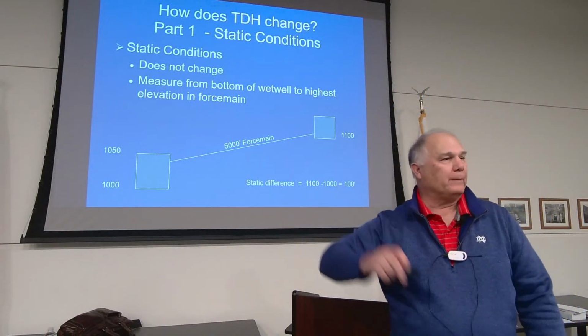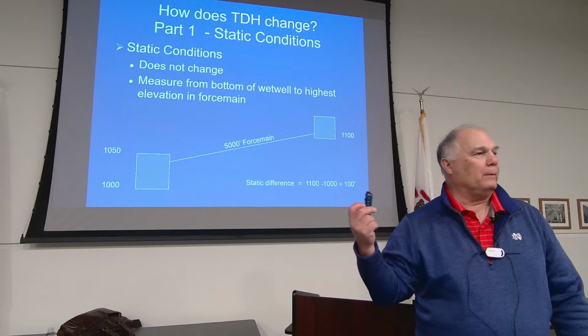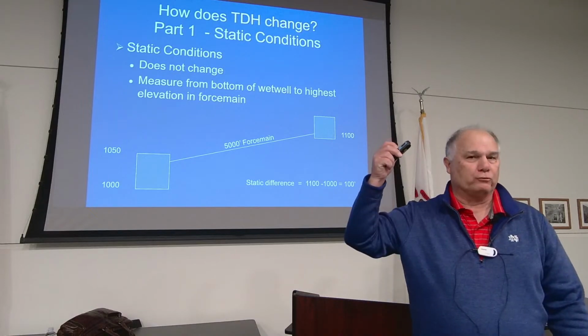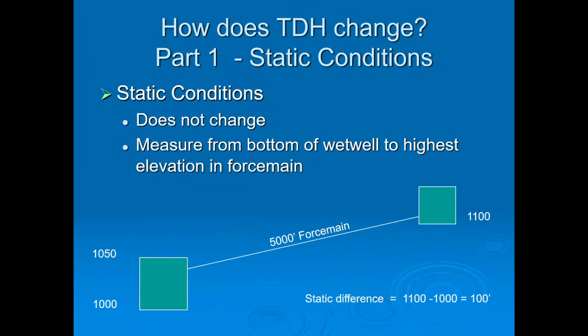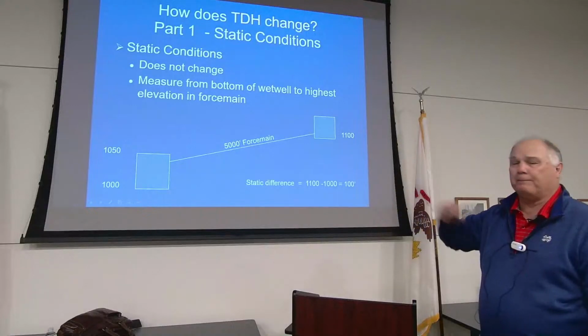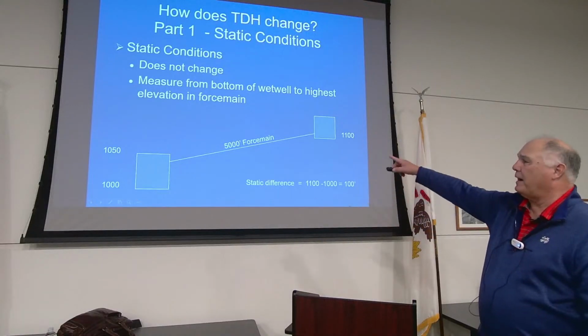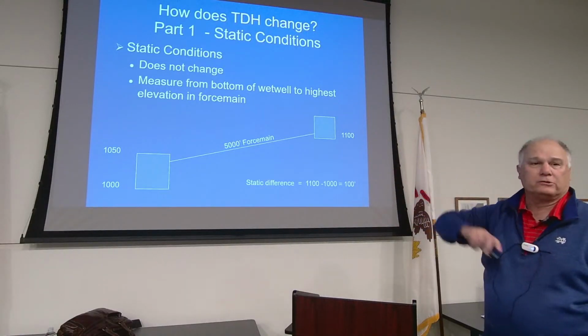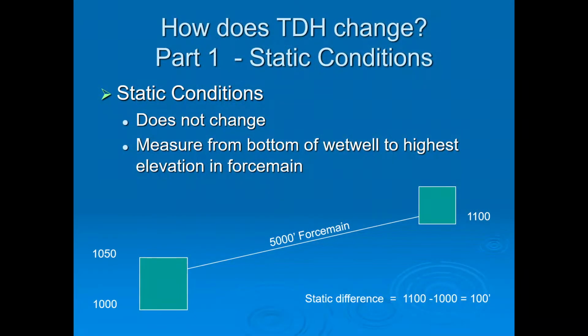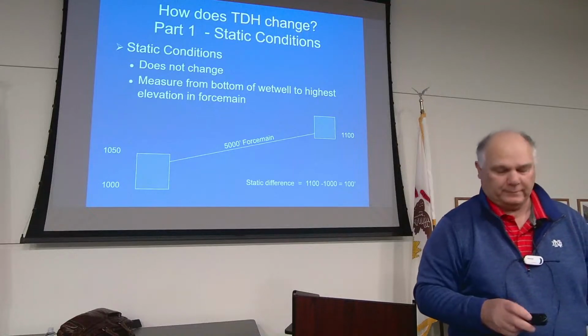We've got one going up the street. We've got a wet well on the left. We're pumping it straight uphill to the wet well on the right. That static is going to be 100 feet. I always take the static from the bottom of the wet well to the highest point in the force main, or in this condition, the top of where we're going to go to gravity sewer from that point, or 100 feet.